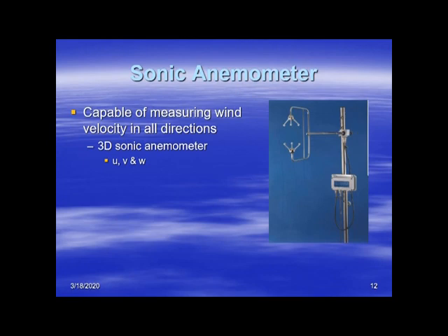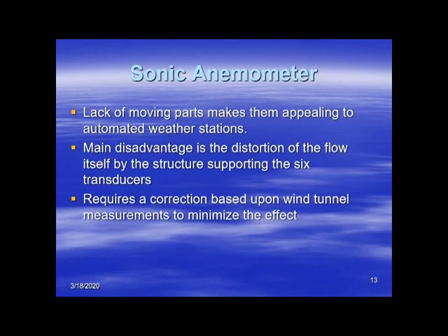Some pluses for the sonic anemometer: there are no moving parts, so these are great for automated weather stations. A minus is that some of the structure around the sonic anemometer disrupts the airflow, which needs to be worked out. They typically put it in a wind tunnel to figure out the errors and then include a correction in the microprocessor — a bit of logic that if the wind is a certain speed and direction, it corrects for that.